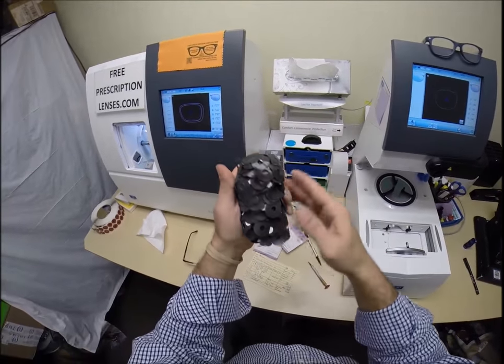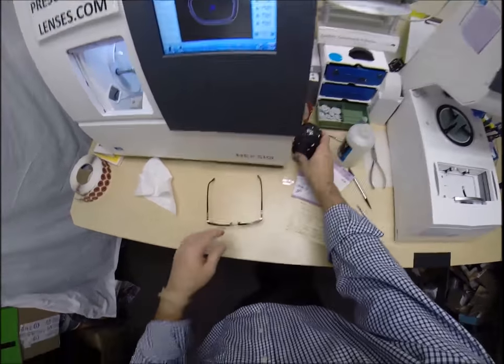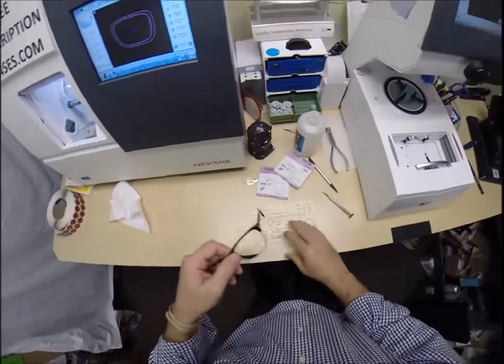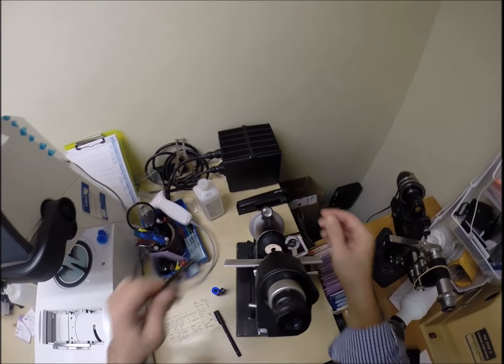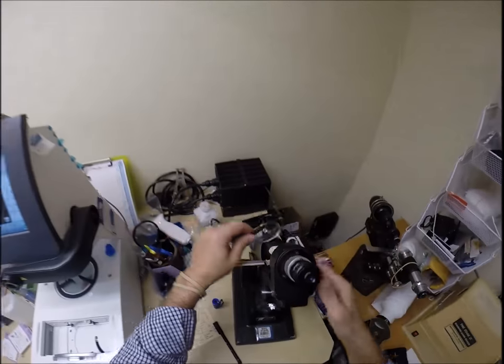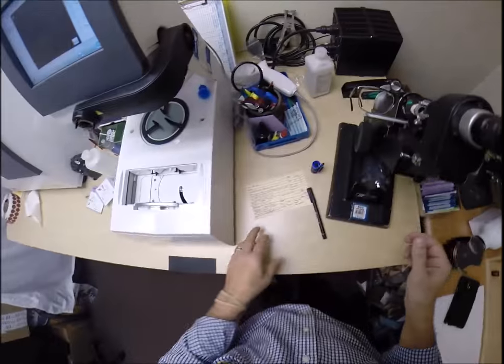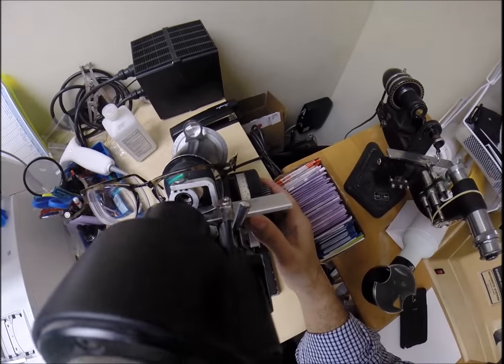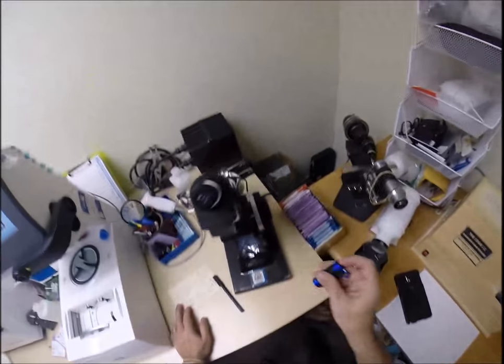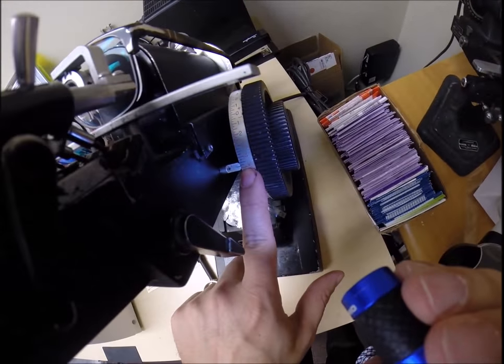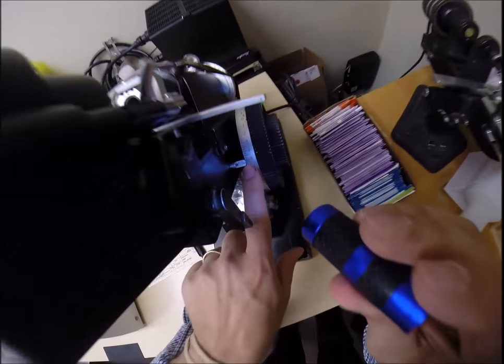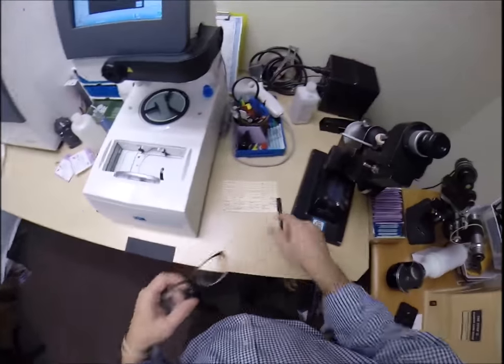And let me grow my monster. It's growing. It looks like the little Snapchat thing in black though, doesn't it? Okay. So we're going to come down here, spin the fine-tune knob to 30, put the lens in just above that black dot and read the power. And I am getting minus 4.75, one tick mark away from five. Now you have 4.75. You have two steps of astigmatism correction, which we'll check for. And we end up at minus five and a quarter. So that is cut perfectly. I couldn't do a better job myself if I had cut these lenses. Wait, I did cut these lenses.